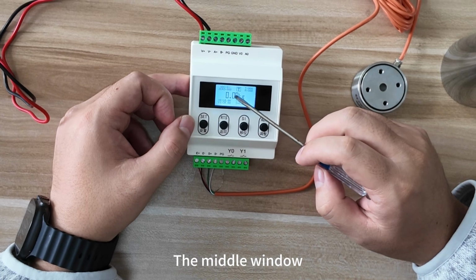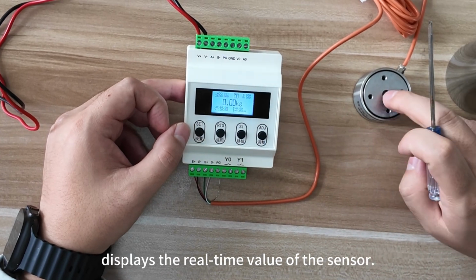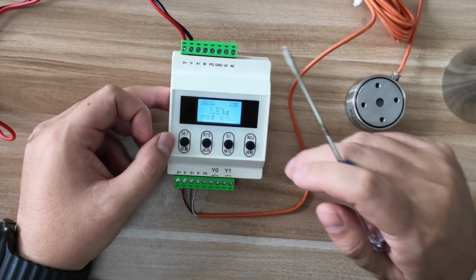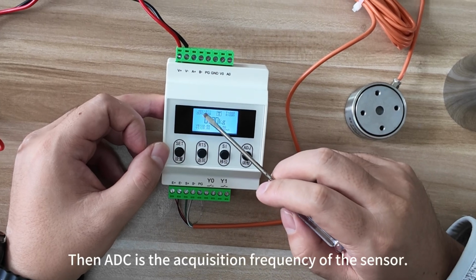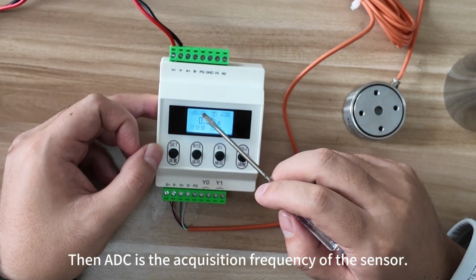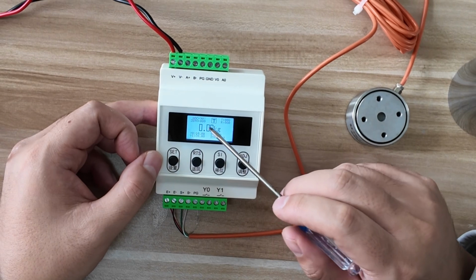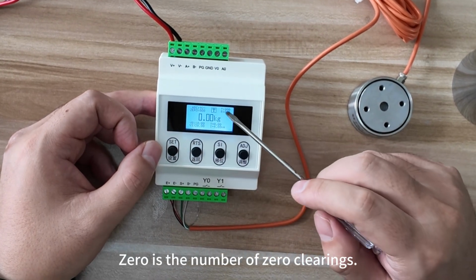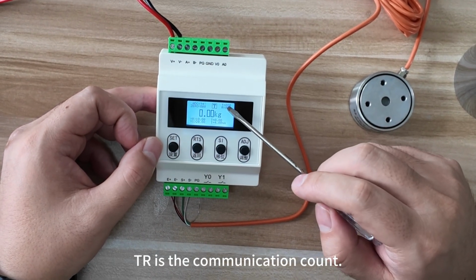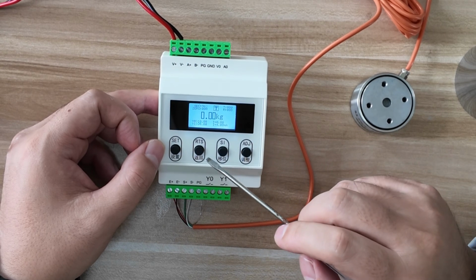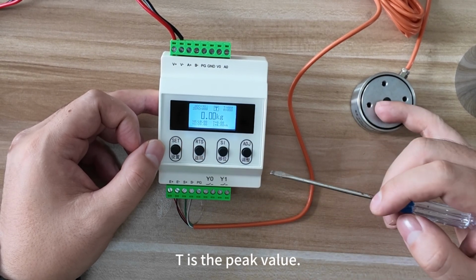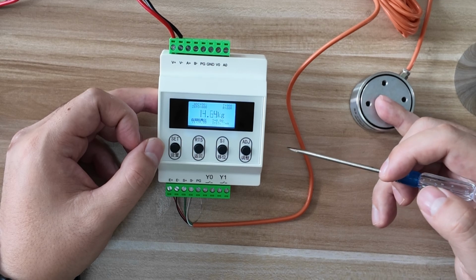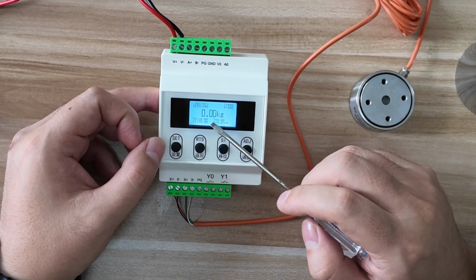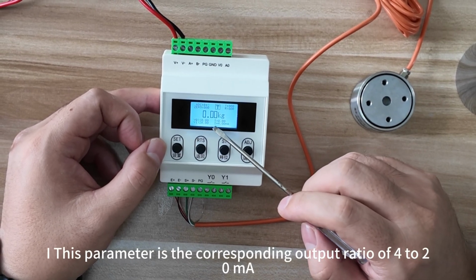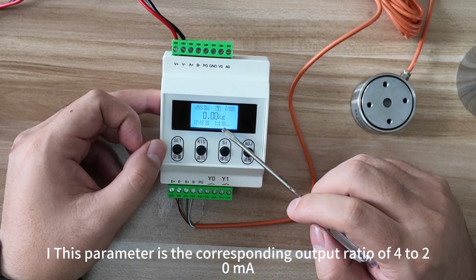The middle window displays the real-time value of the sensor. Then ADC is the acquisition frequency of the sensor. 0 is the number of zero clearings. TR is the communication count. T is the peak value. This parameter is the corresponding output ratio of 4 to 20 milliamperes.